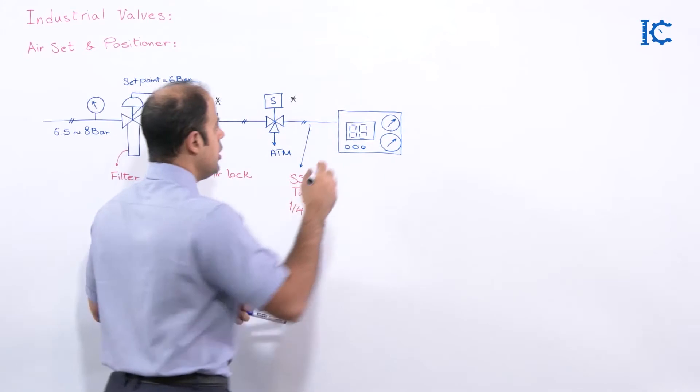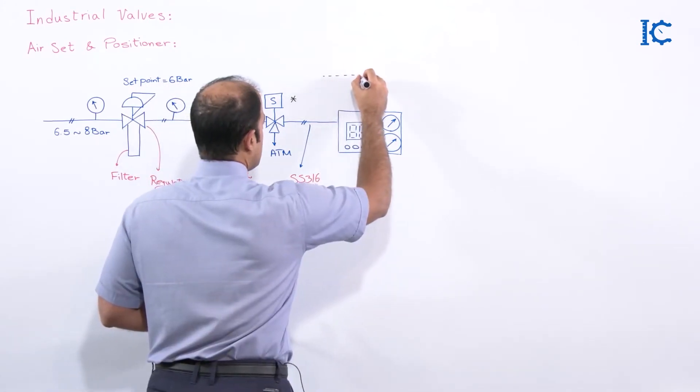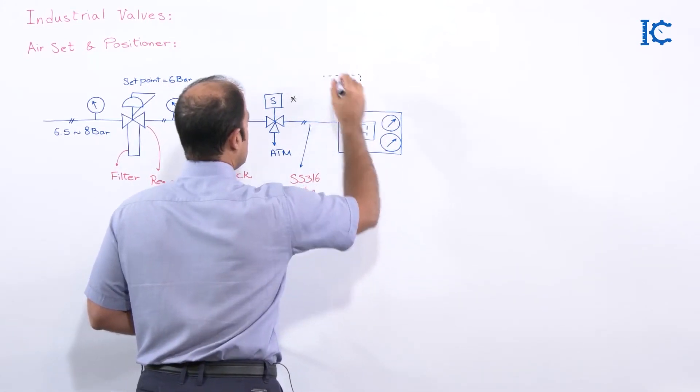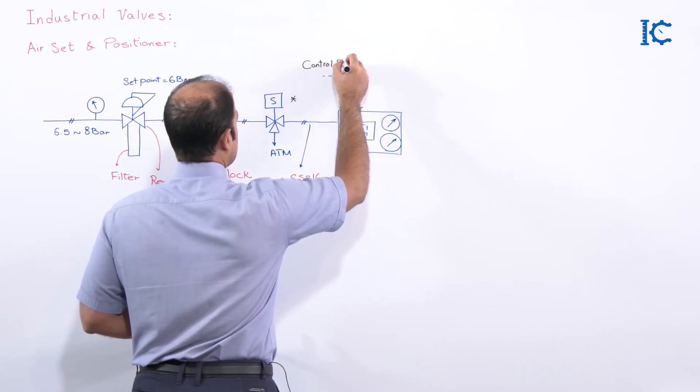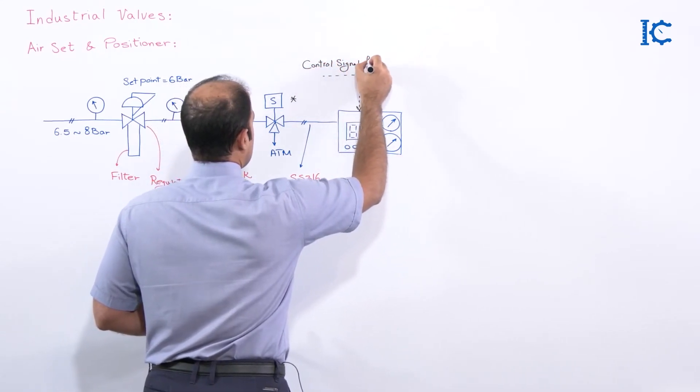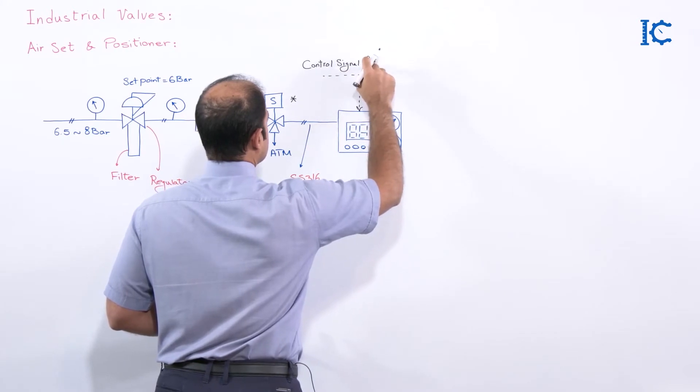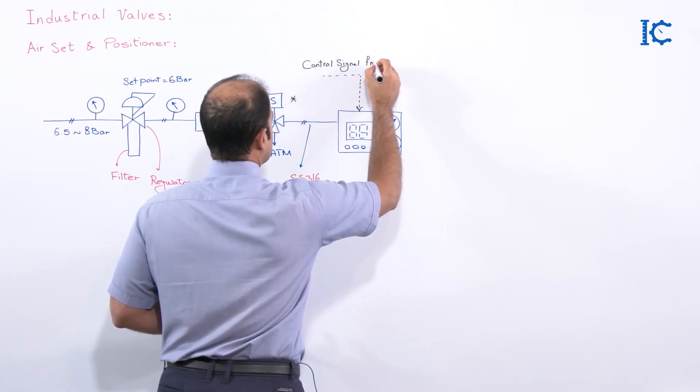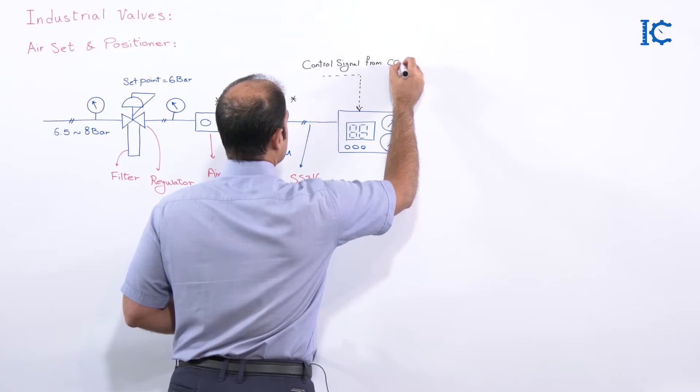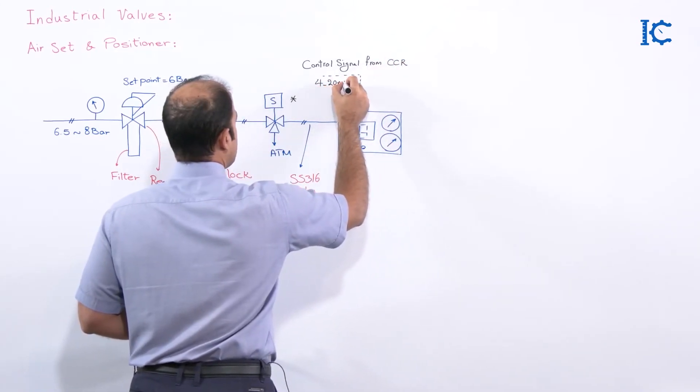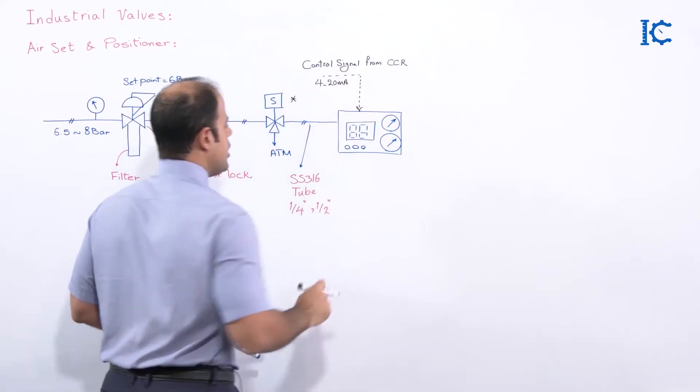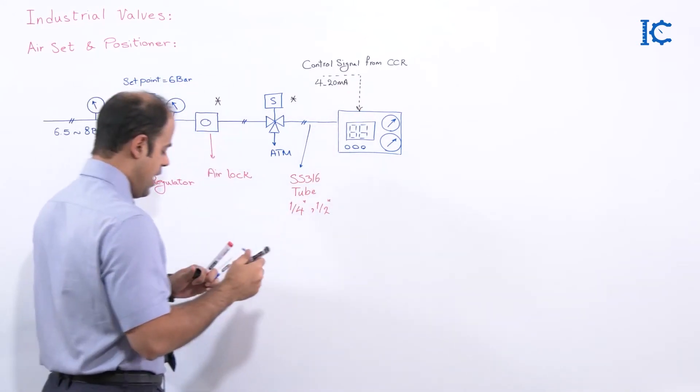As you know, there must be a control signal from control room, from the central control room, and as you know that it's 4-20 mA. It sends to the positioner and after that the outlet tube is going to be connected to the actuator.